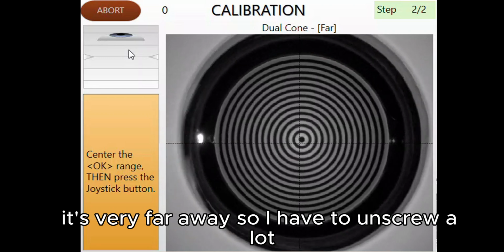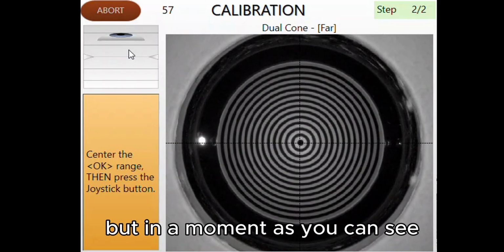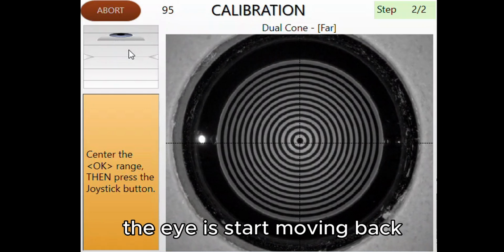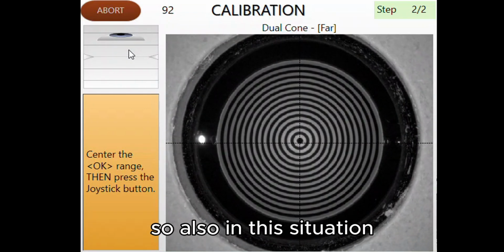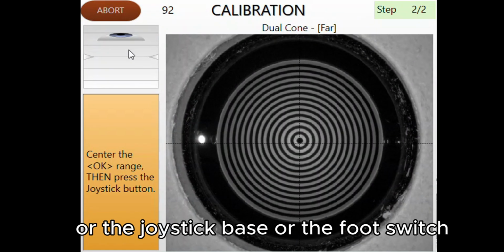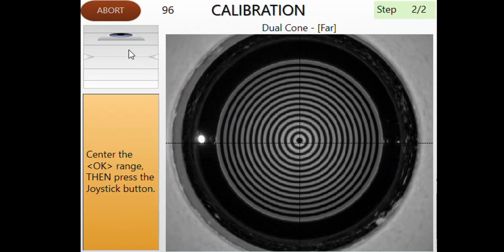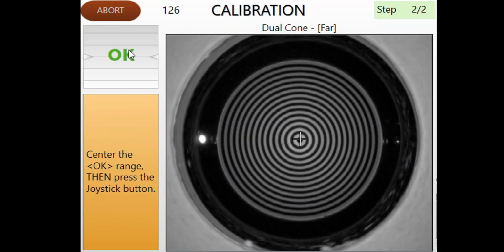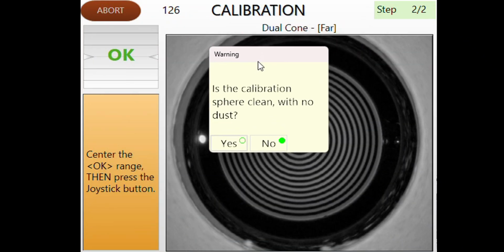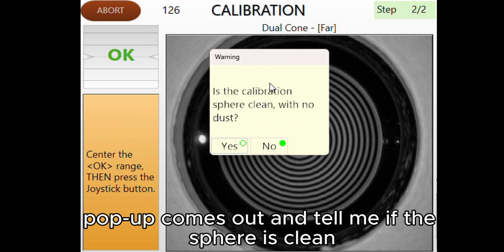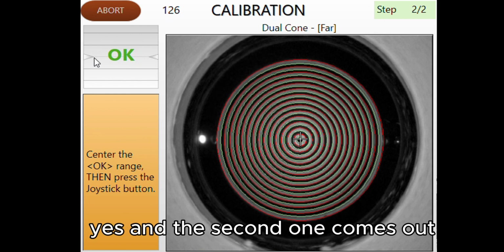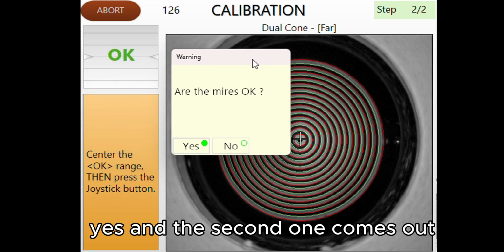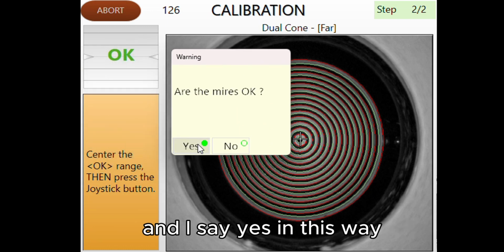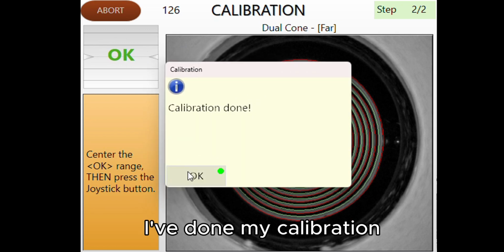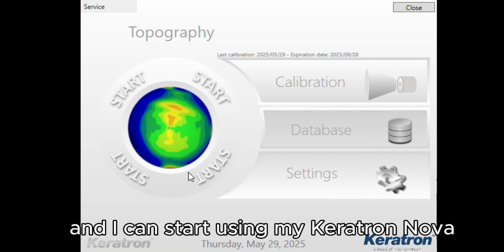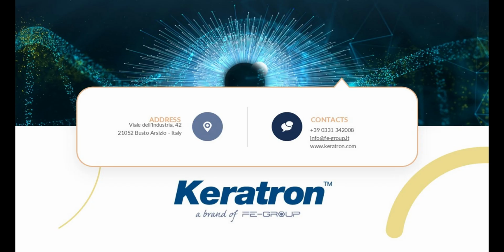It's very far away, so I have to unscrew a lot. But in a moment, as you can see, the eye starts moving back. So also in this situation, I keep on pressing the button, or the joystick base, or the foot switch, and I keep on unscrewing. I reach the OK, a pop-up comes out and tells me if the sphere is clean, yes, and the second one comes out asking me if the mires are okay, and I say yes. In this way, I've done my calibration, and I can start using my Keratron NOVA.